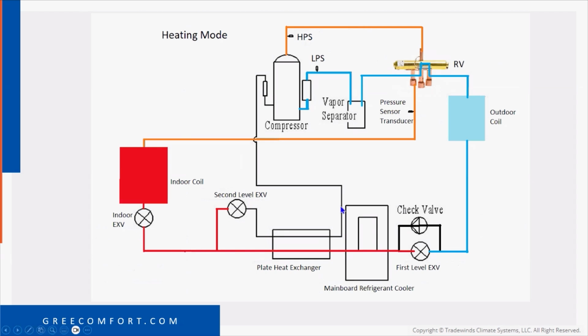So if we take liquid refrigerant and meter it through here into this plate type heat exchanger and absorb heat out of this liquid line, we're actually dumping that back into the compressor so that we can take the heat that we didn't release on the indoor coil, pull some of that out of that liquid temperature and actually put it back in the compressor and compress it again for low ambient heating, okay? It's quite different than from what they were doing with the 410A version of the FLEXX.